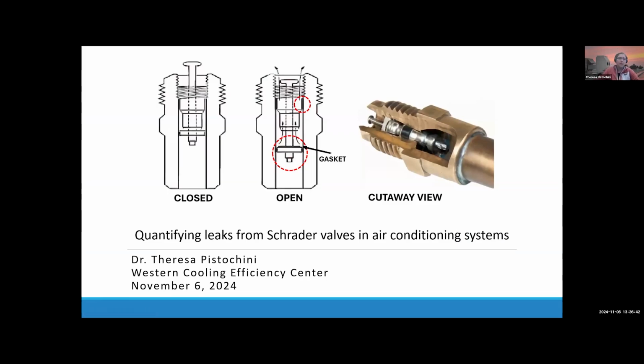All right, so I want to share with you two topics today that I thought were both important to facility management. The first one is how to think about leaks in HVAC systems that we attribute to Schrader valves. A Schrader valve is a service access port for adding or removing refrigerant from an HVAC system. Essentially, when you connect your refrigerant hose, it pushes down this pin, which opens up a valve here, and the refrigerant can flow in and out.